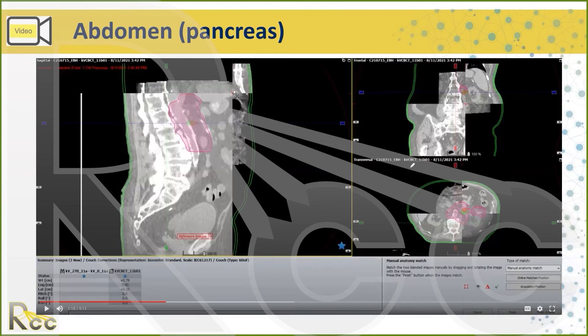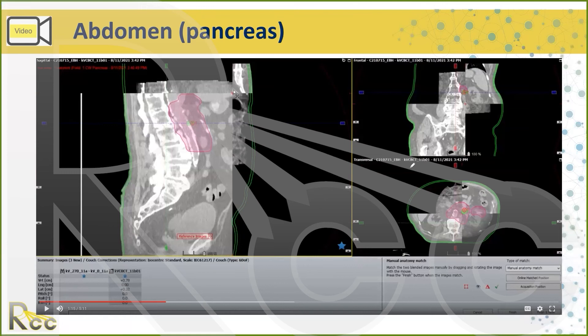If you're ever concerned that the geometry doesn't match because you did a five-millimeter planning slice and you're now doing a 2.5-millimeter cone beam slice, that should match up fine — but you can always use the KV to verify you're not slightly off. If there were any misregistration based on slice thickness, you'd be off on the longitudinal axis, so you could take a KV image afterwards to verify. It's actually something I struggled with when I first started doing these.